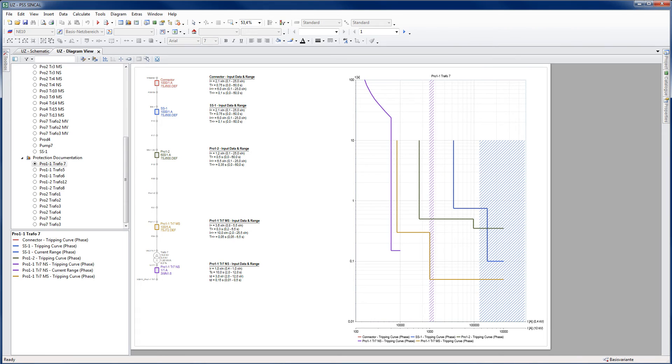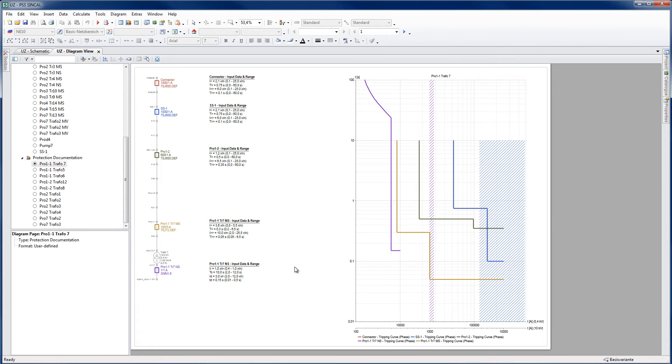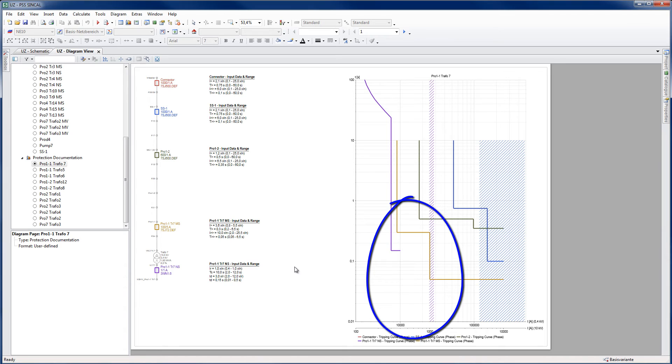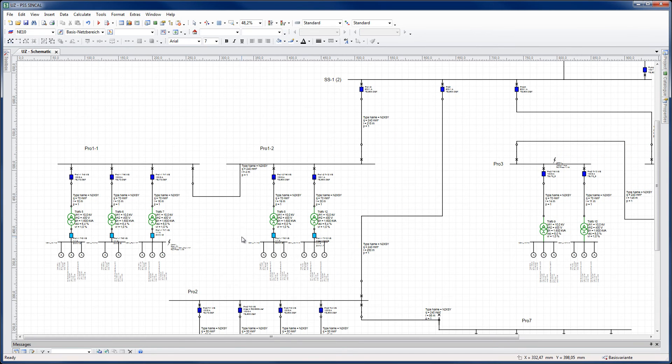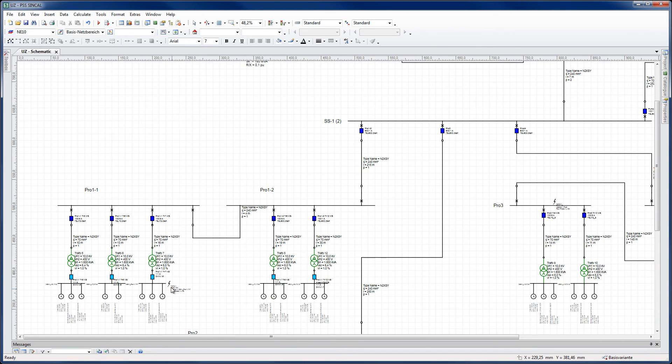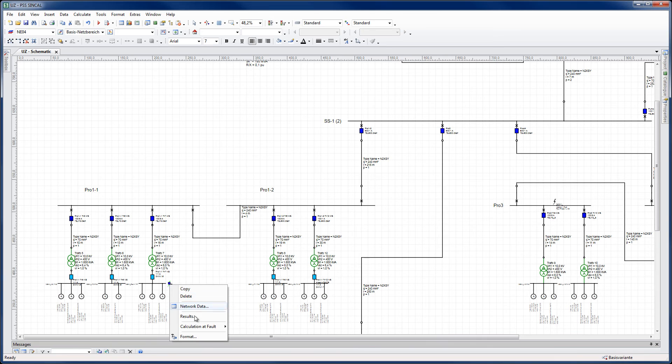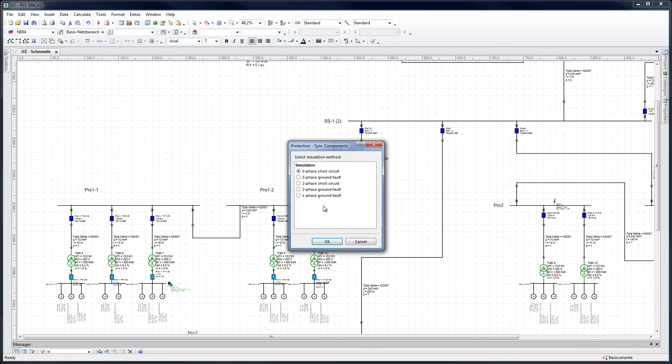From the grading diagram, it can be seen that current settings are not adequate in many respects. For instance, short circuits in the low voltage level are not selectively cleared. This can be verified in the simulation mode using PSS SINCAL's inbuilt fault clearance analysis. Consider simulating a three phase fault at this bus bar.